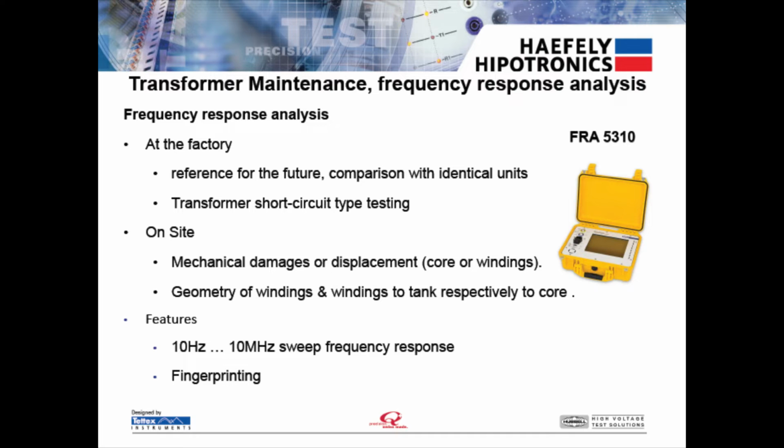Frequency response analysis, or FRA, is best described as a fingerprint of that transformer, like an electrical mechanical fingerprint within the system. So it should always be the same as long as the connections are made at the exact same site. So if it differs as the transformer ages, it reveals mechanical damages and displacements.